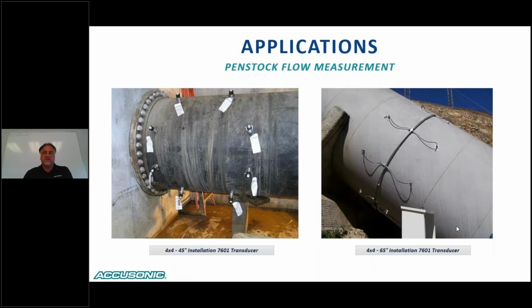The other nice thing about the 65 degrees, we typically try to utilize 45 degrees just because the cosine of the path angle is much less sensitive at 45 degrees than it is at 65 degrees. But if you have a tight constraint from the ball valve to the scroll case, that's very short axially, that 65-degree path angle will actually reduce the length and maybe potentially fit in that location.